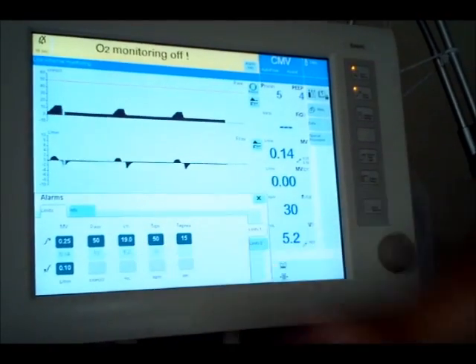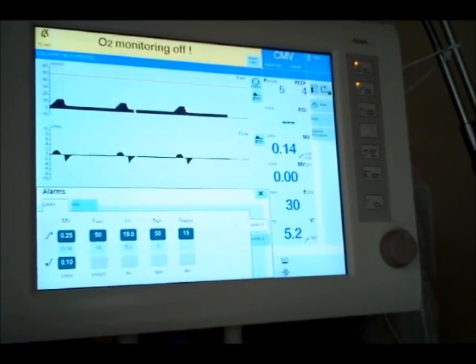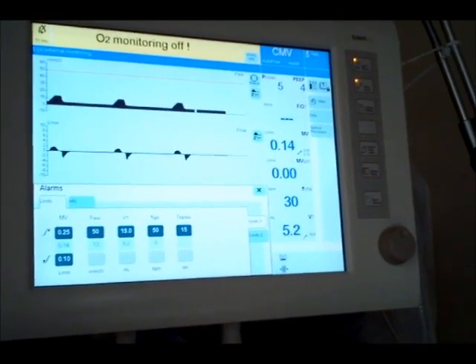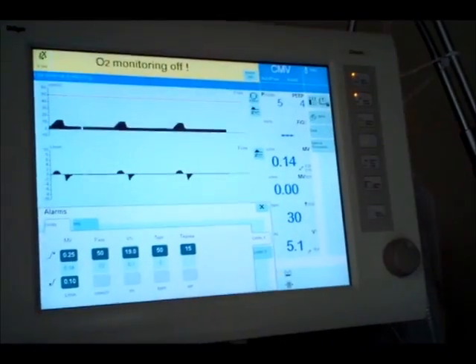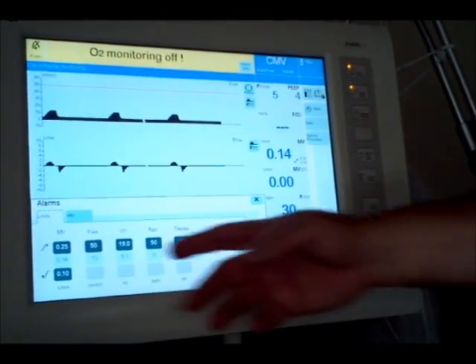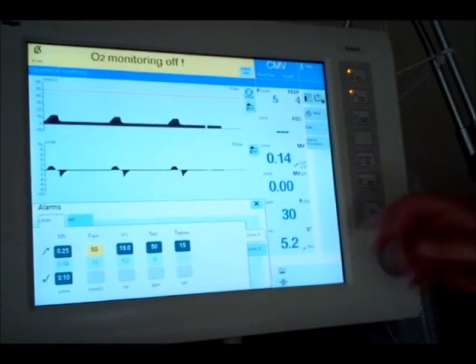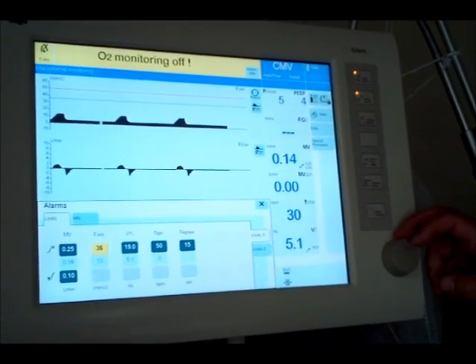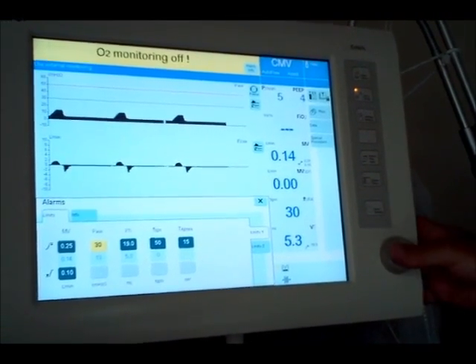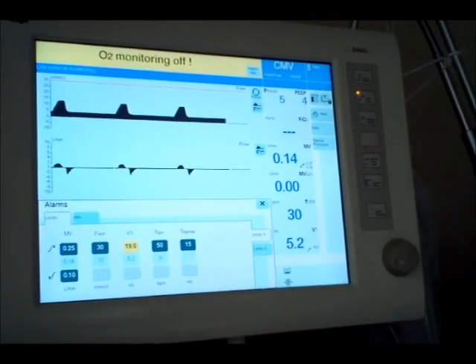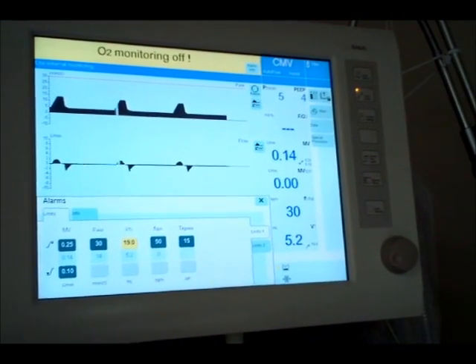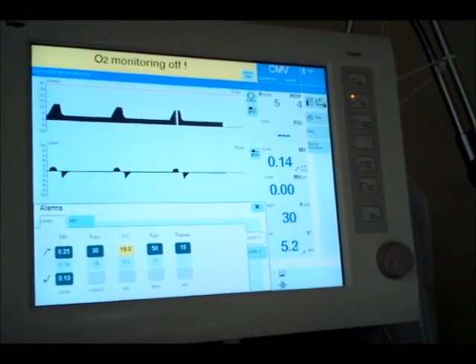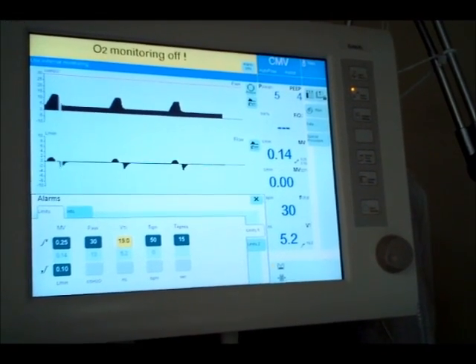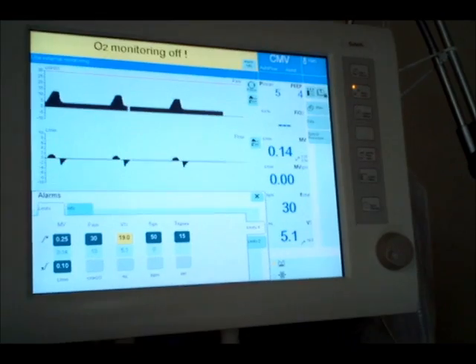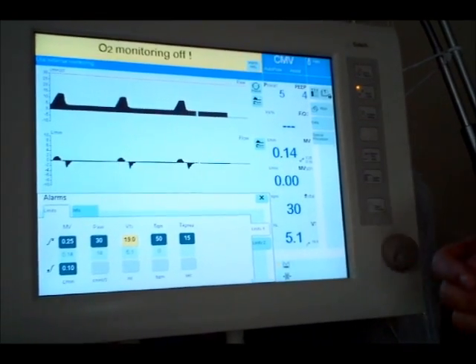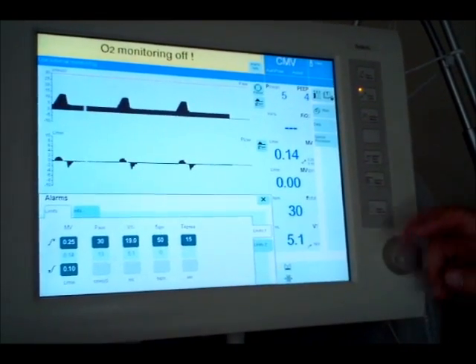Okay, right now with the tidal volume of 5, my peak pressure is only 14, 13. So I may set this pressure limit here at maybe 30. My high tidal volume alarm, which this is the only ventilator you really have one of those. Right now my tidal volume reading is about 5.2. General rule of thumb is to set that 1.5 to 2 times. Maybe I'll pick 9.